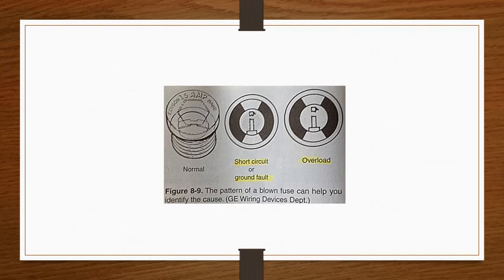If the first condition is the cause, place the higher wattage appliances on separate circuits. Any overworked motors, especially furnace blower motors, may need to be repaired or replaced. Machines with excessive ampacity should be easy to find.